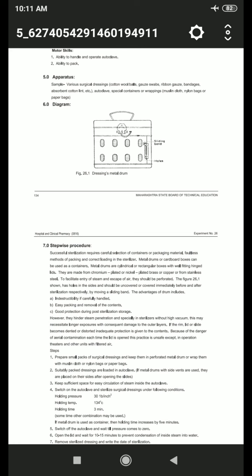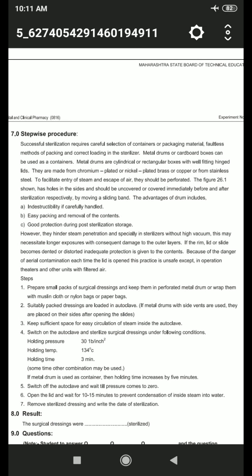Successful sterilization requires careful selection of the container or packing material, flawless method of packing, and correct loading of the sterilizer. Then metal drum or cardboard boxes can be used as a container. Metal drums are cylindrical or rectangular boxes with well fitted hinged lids. Okay, they are made from chromium plated or nickel plated brass or copper, or from stainless steel. To facilitate entry of the steam and escape of the air, they should be perforated.